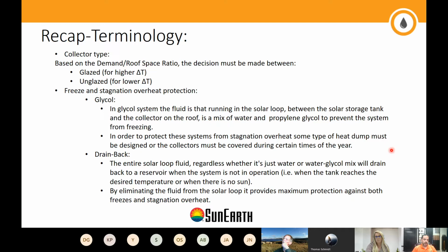In an indirect glycol system, what protects you against freezing is the mixture of propylene glycol and water in your solar loop. To protect against stagnation overheat—especially in colder climates where you need a lot of performance in winter but not summer—a proper heat dispensing mechanism has to be designed in, because overheating combined with glycol can cause a lot of problems if it goes on too long.